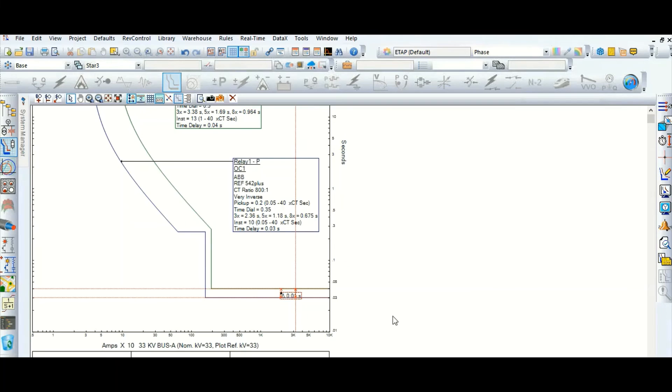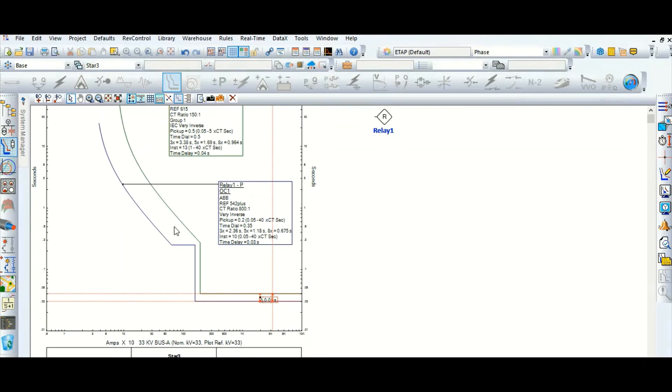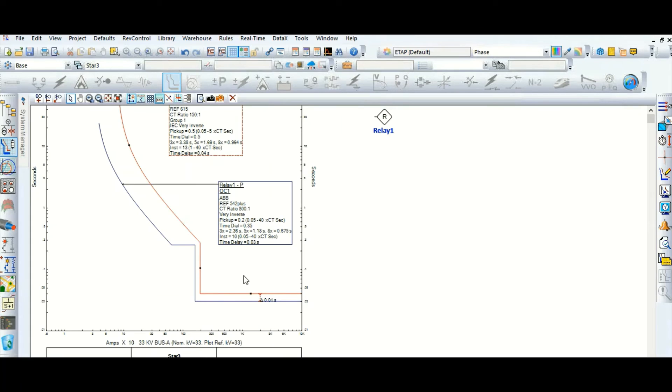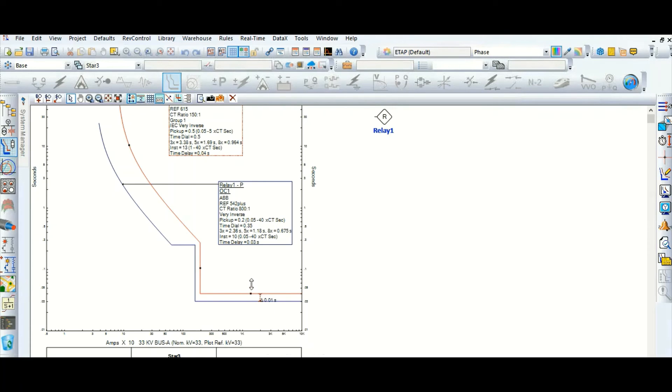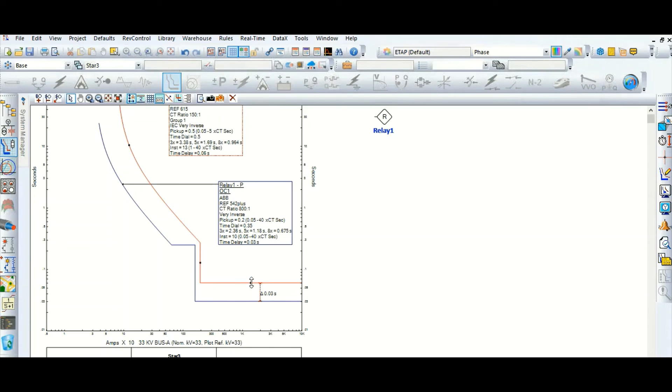What we need to do, we need to increase the time dial here for relay 2. This is now 30 millisecond.